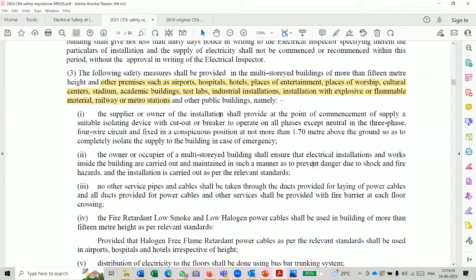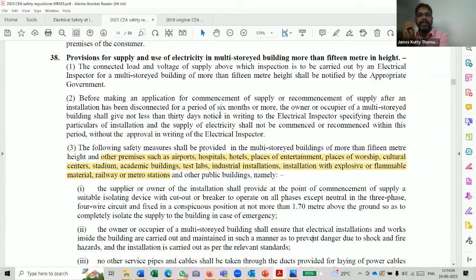Yes. Sir, can I add some point? Yes, please, sir. Sir, actually, this high-rise building means it is entirely a different category. As per NBC, these are the buildings having height more than 15 meter. But in the same NBC, it is said that the height of the high-rise building depends upon the local fire laws. For example, in Bombay, it is 32 meter. In Kerala, it is 60 meter. This regulation 38 is entirely different, which belongs to the multi-storied buildings having height more than 15 meter. That is an entirely different category and not high-rise building.